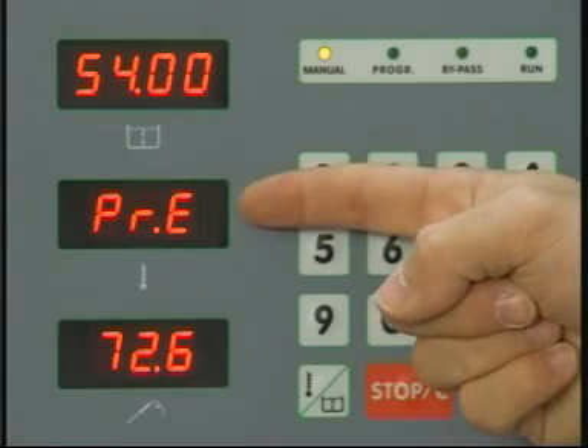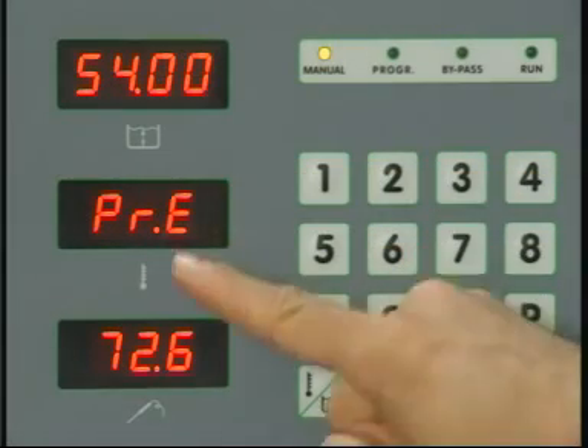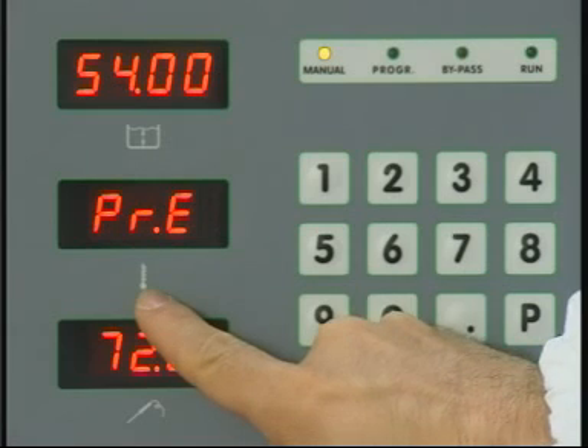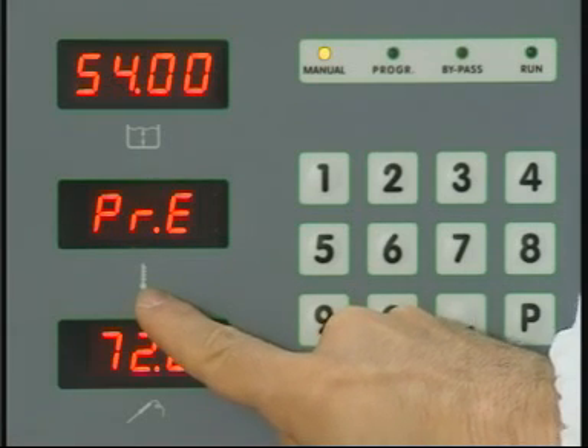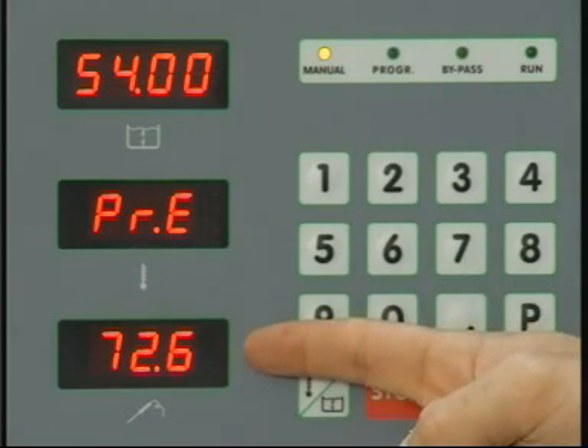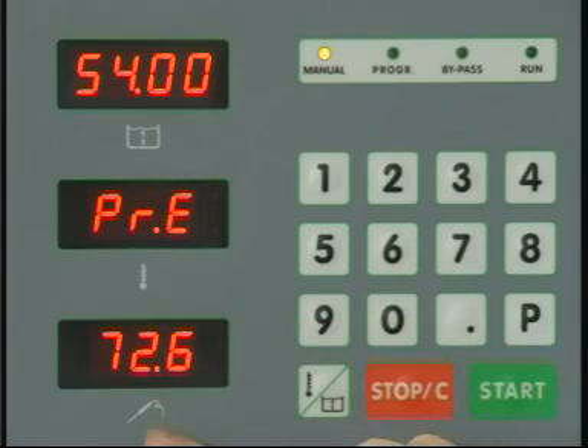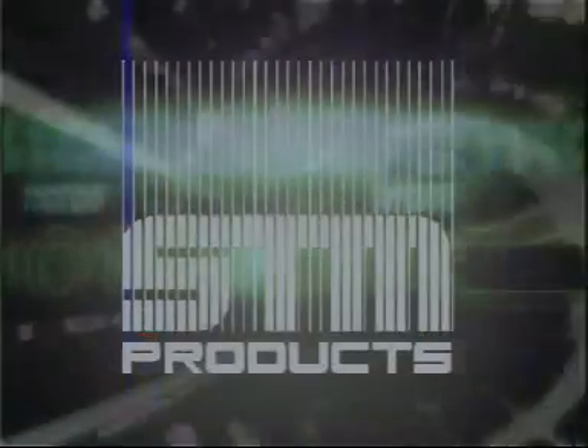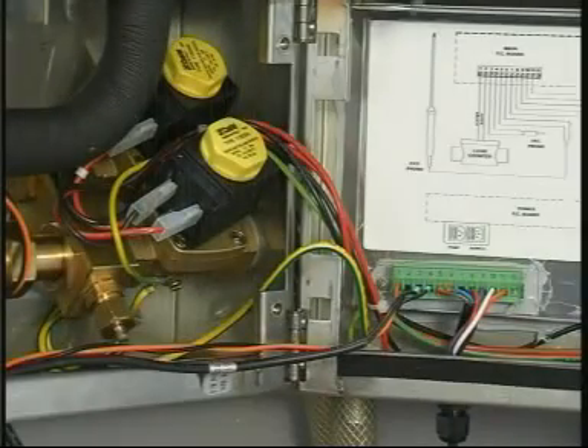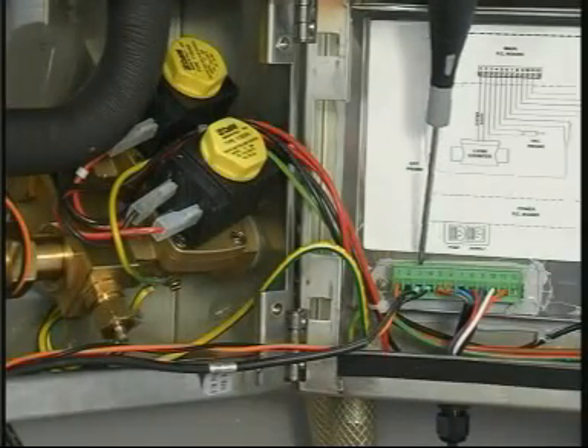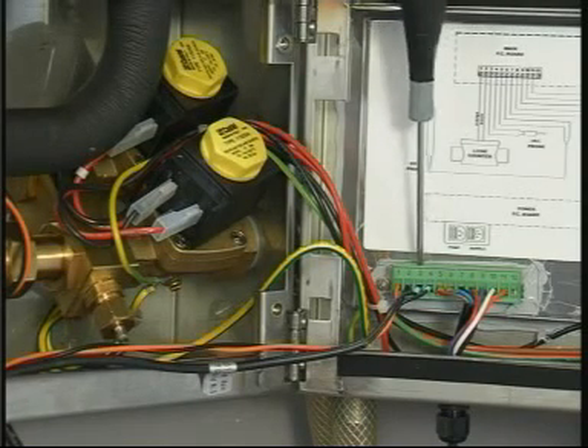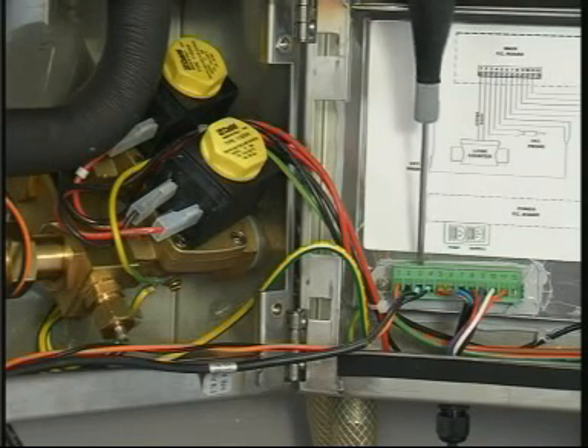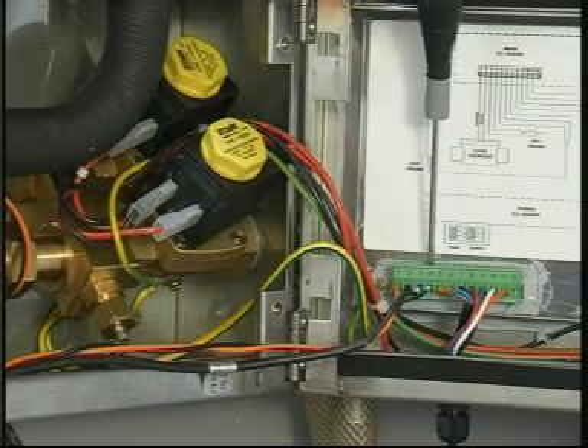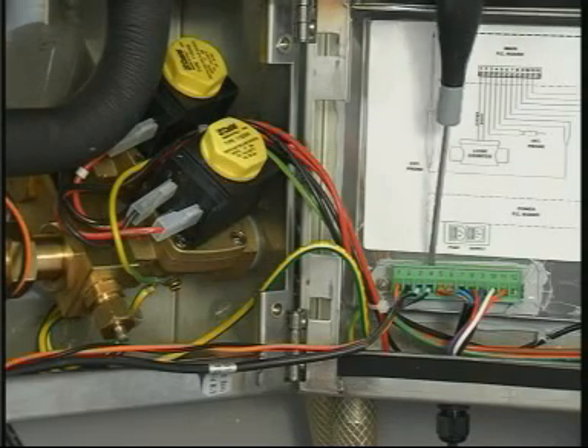Internal probe error. If a fault appears, as in the image, with the message appearing only on the central display, this means that the internal temperature probe is broken or badly connected. Replacement of internal probe. Close the inlet ball gate valves and release the pressure. Switch off the supply to the machine.